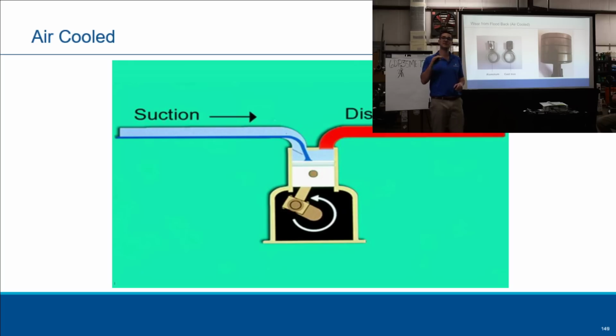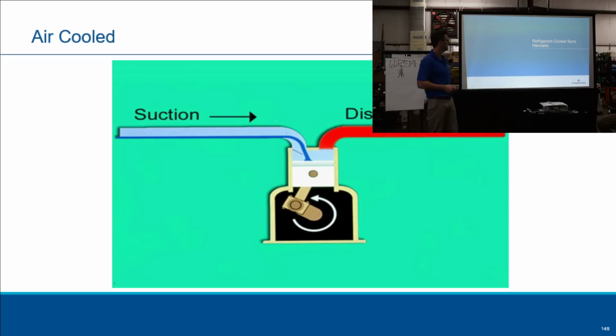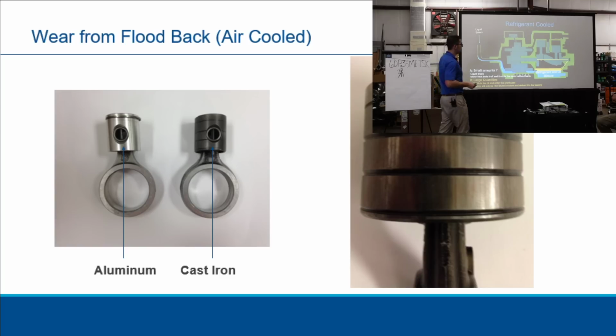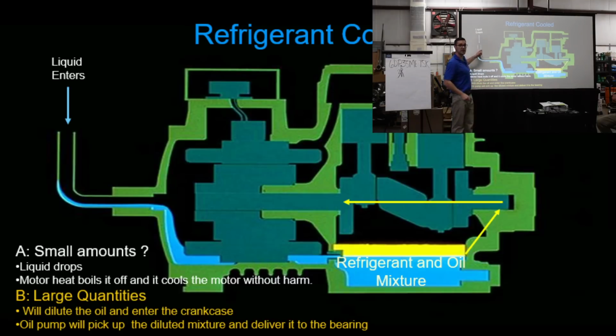Does that make sense? Okay, good. So refrigerant-cooled compressors, your suction's coming in. You have your motor right here. What does the motor do? What does it produce? A lot of what? Heat. A lot of heat, right? So you got some heat in there and you get a little bit of liquid refrigerant in there. Hopefully it'll boil it off. But you get large quantities of liquid.